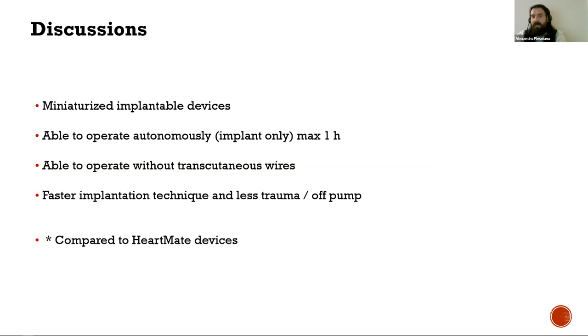There are several features of the proposed device that have the potential to minimize the complications associated with the market available devices. The main blood path does not cross the space between stator and rotor. The magnetic bearings allow reliability and reduce the risk of cell damage. The amorphous tetrahedral carbon coating reduces the risk of rejection and reduces friction between blood and the pump surfaces.